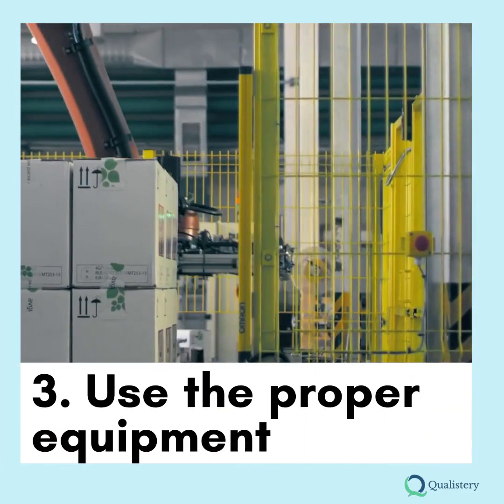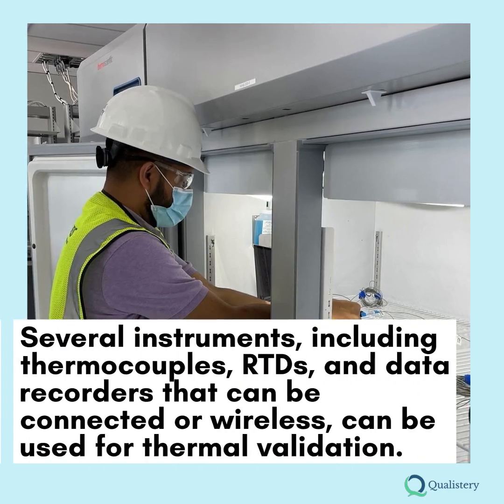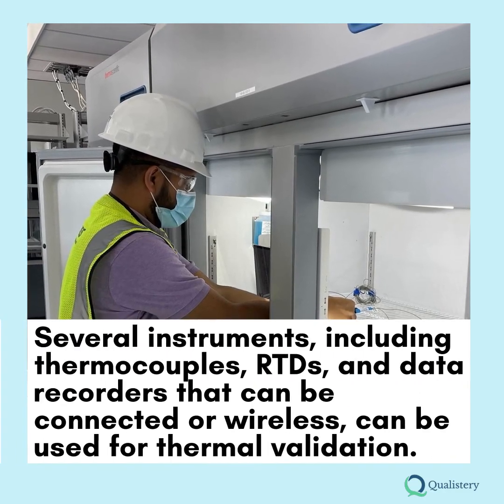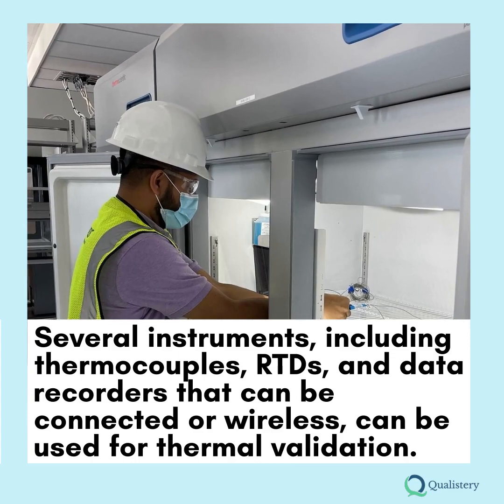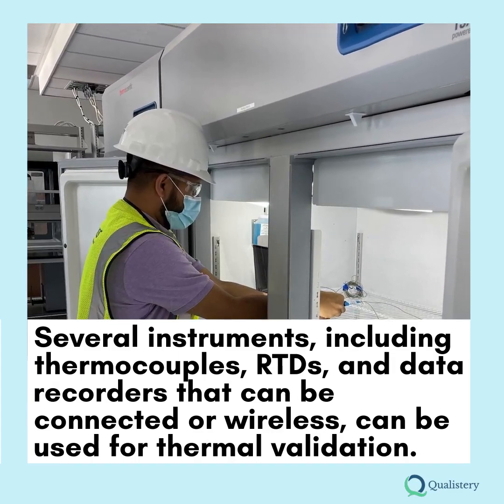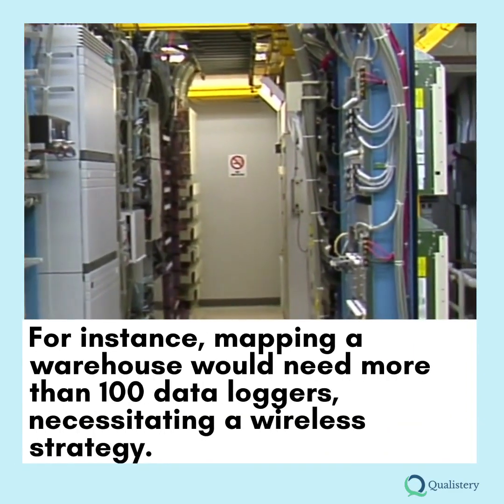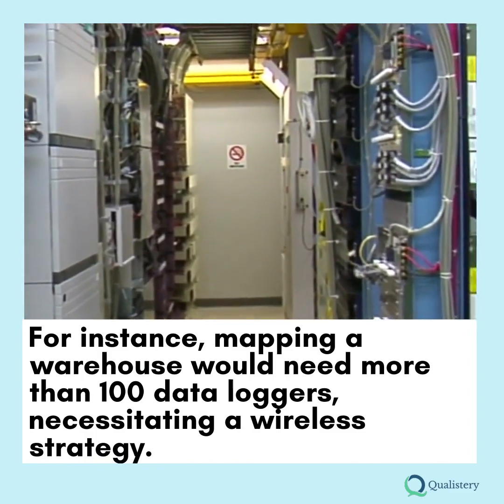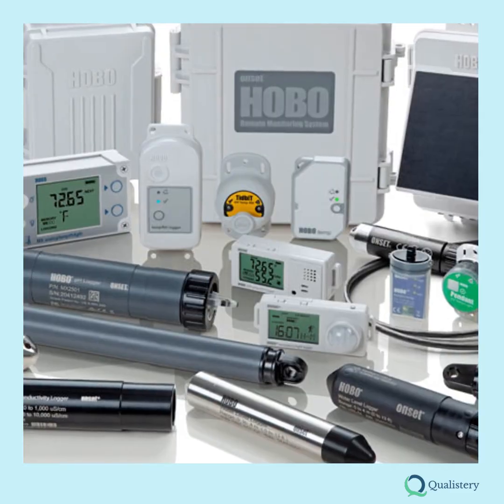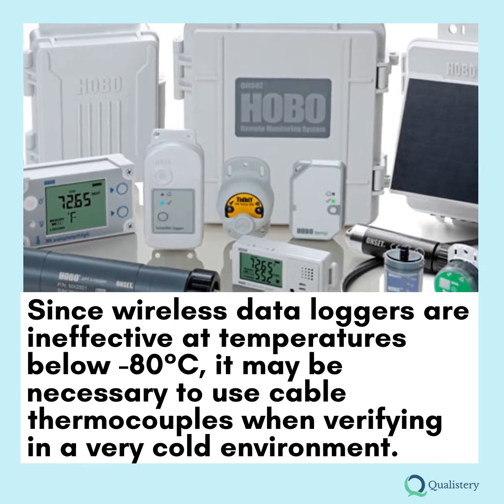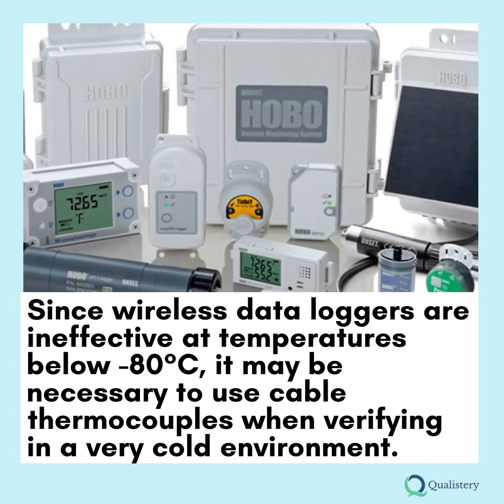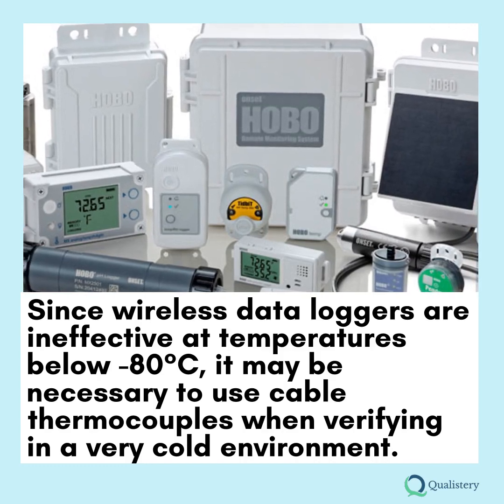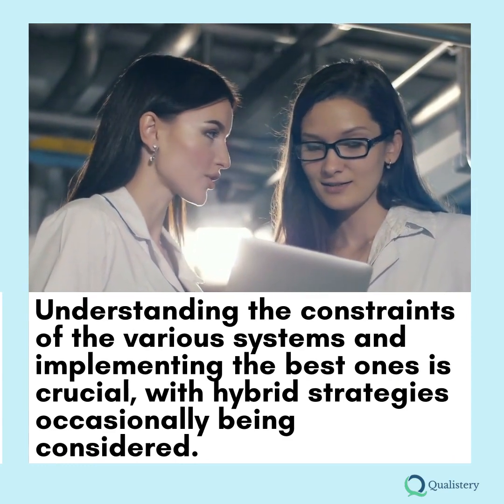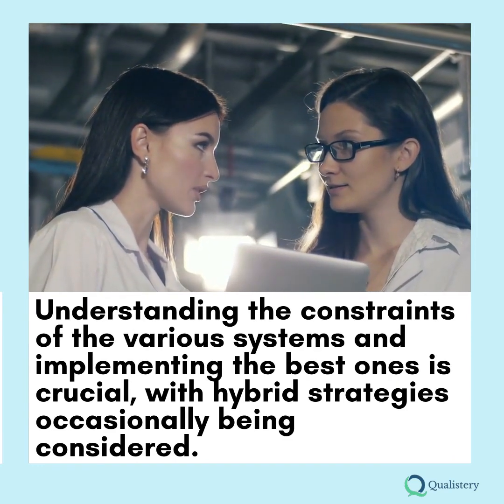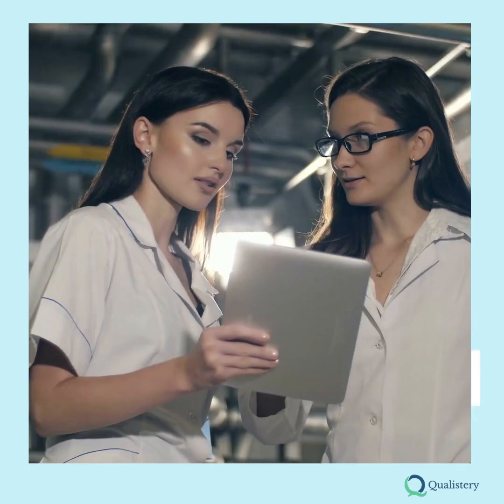3. Use the proper equipment. Several instruments, including thermocouples, RTDs, and data recorders that can be connected or wireless, can be used for thermal validation. For instance, mapping a warehouse would need more than 100 data loggers, necessitating a wireless strategy. Since wireless data loggers are ineffective at temperatures below -80 degrees Celsius, it may be necessary to use cable thermocouples when verifying in a very cold environment. Understanding the constraints of the various systems and implementing the best ones is crucial, with hybrid strategies occasionally being considered.